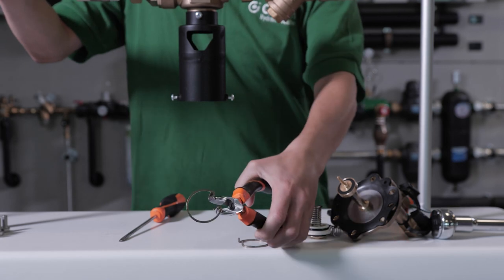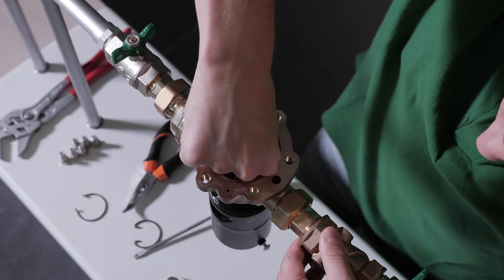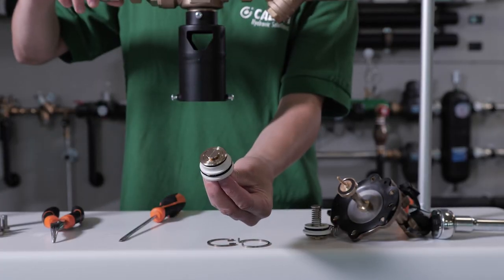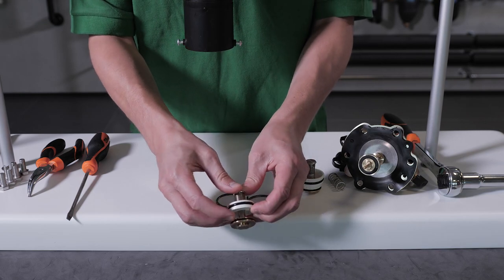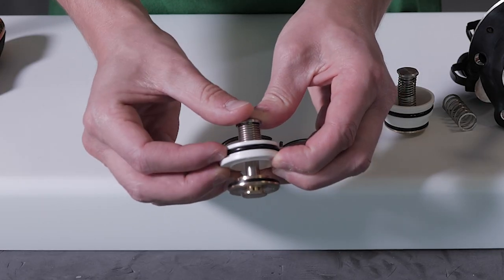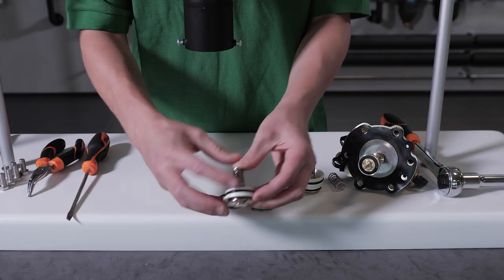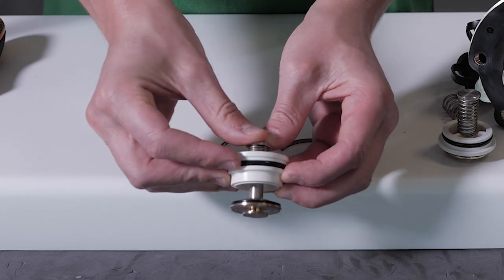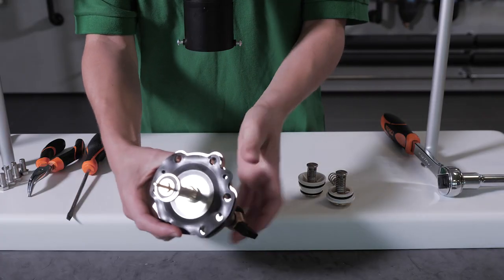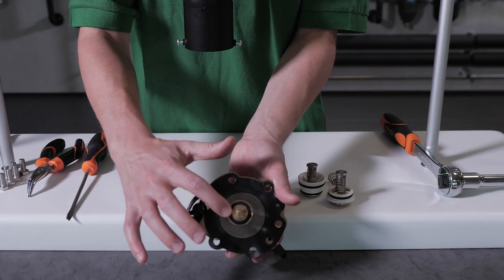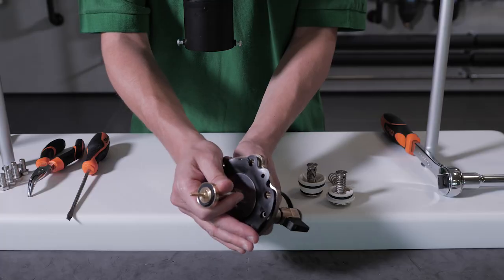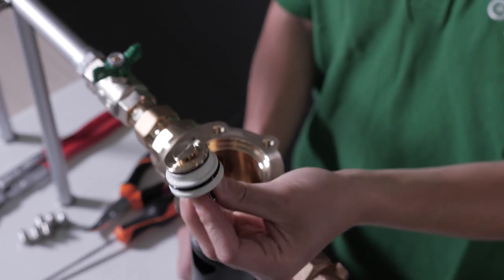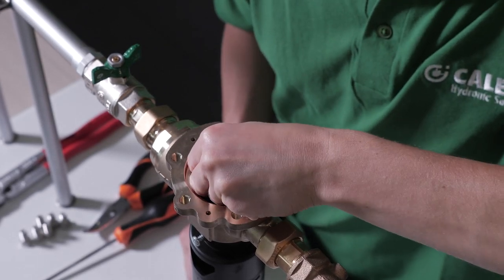clip of the downstream check valve and remove the whole check valve from the valve. Pay attention to the status of the seat, the discharge valve, and the status of the diaphragm. Once the check valves have been cleaned or replaced, we can put them back.